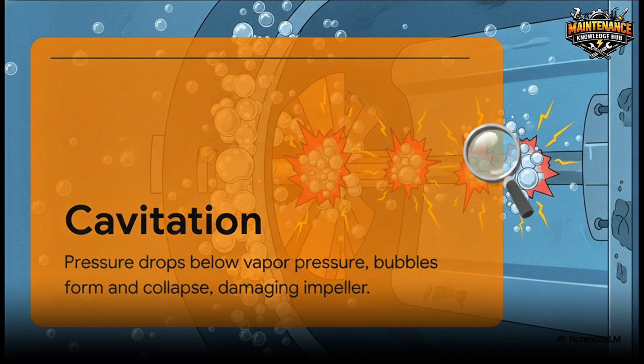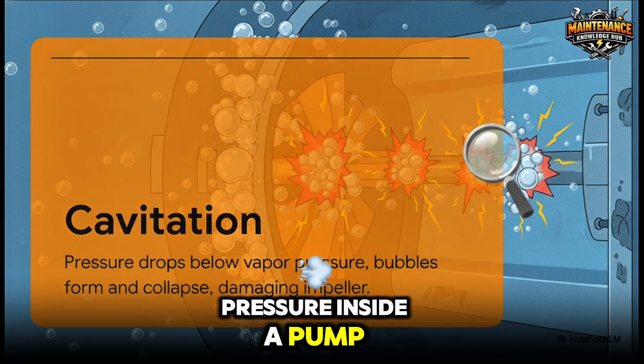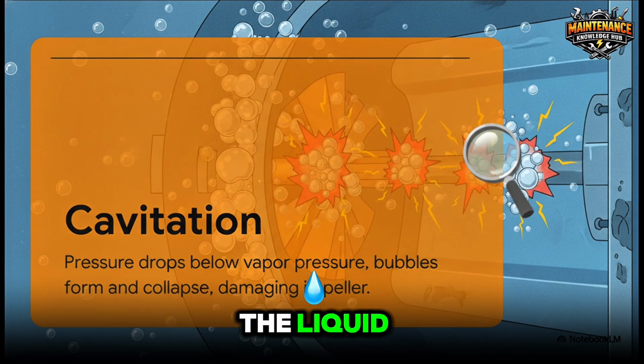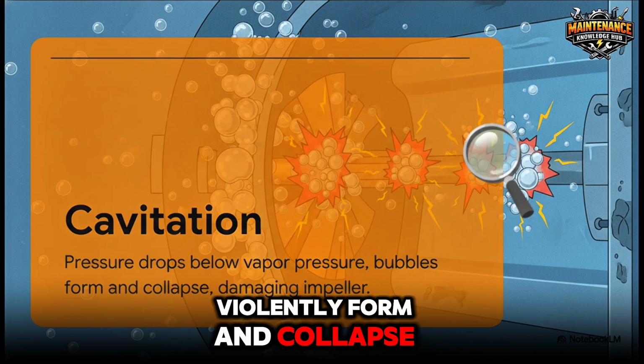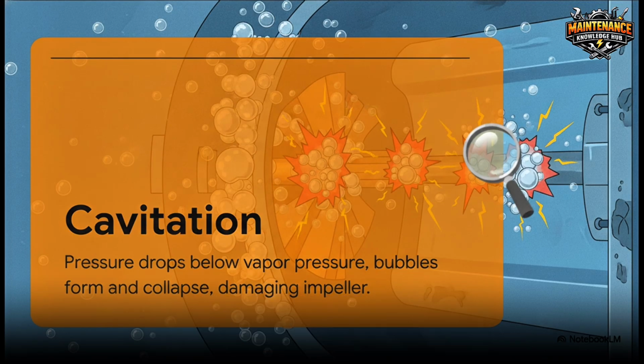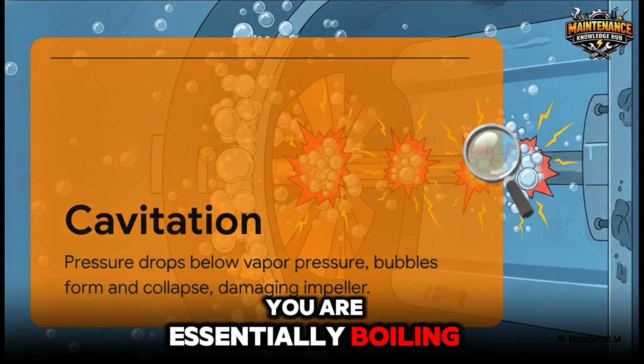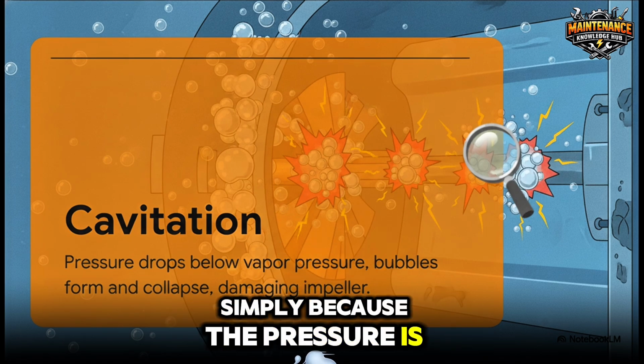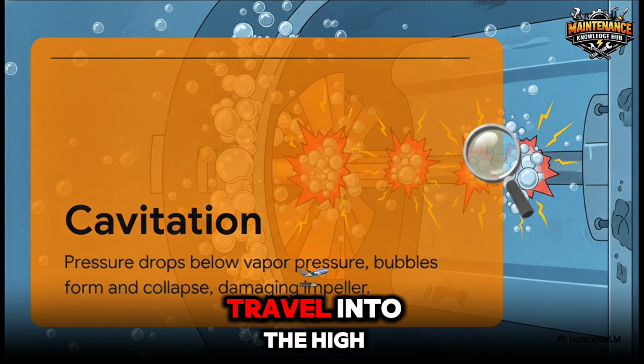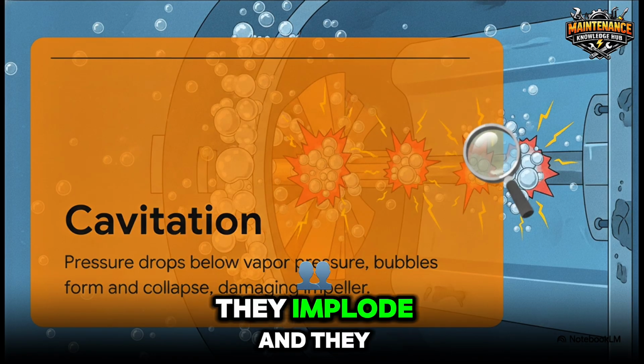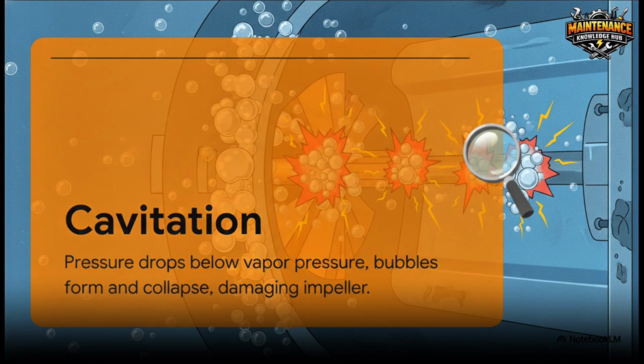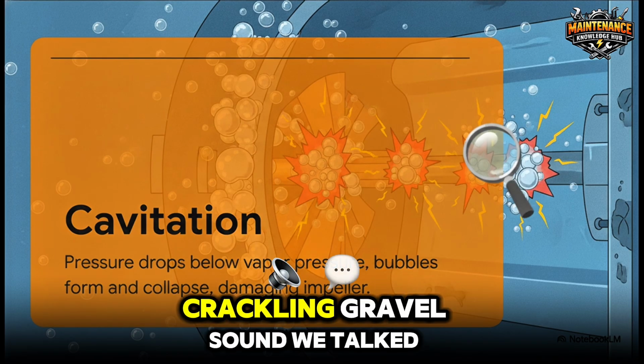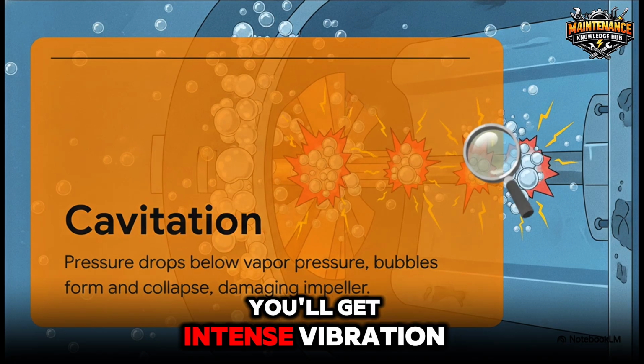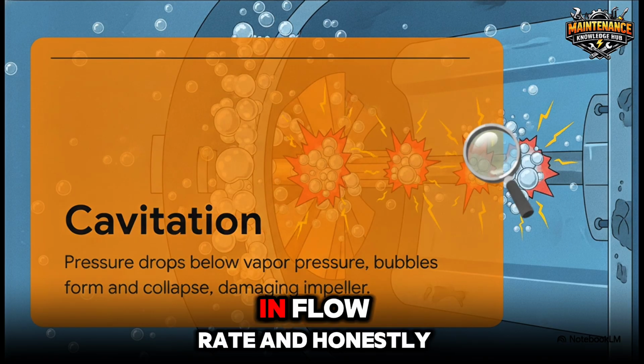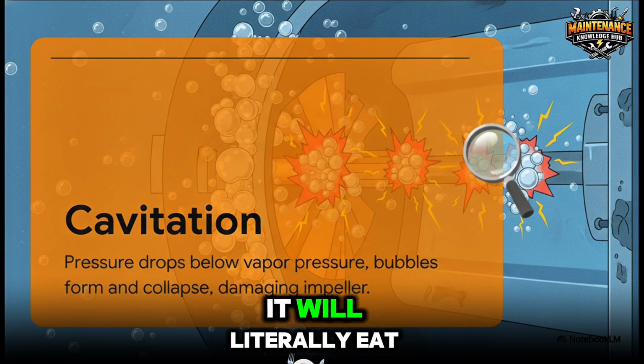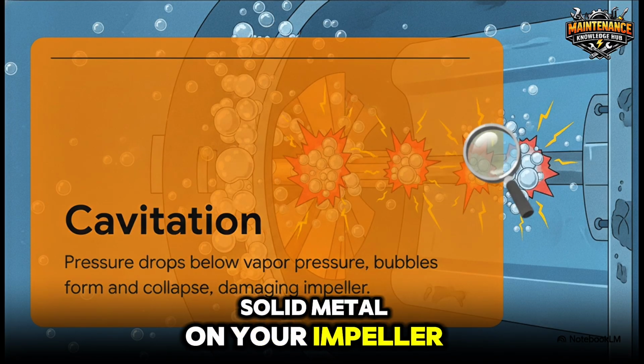So what is it? Cavitation happens when the pressure inside a pump drops below the vapor pressure of the liquid, causing air bubbles to violently form and collapse, which then damages the impeller. Think about that. You are essentially boiling the liquid at room temperature simply because the pressure is so low. When these little bubbles travel into the high-pressure side of the pump, they implode, and they do it with incredible force. Physically, this manifests as that loud crackling, gravel sound we talked about earlier. You'll get intense vibration, a sudden massive drop in flow rate, and honestly, if left unchecked, it will literally eat away chunks of the solid metal on your impeller.